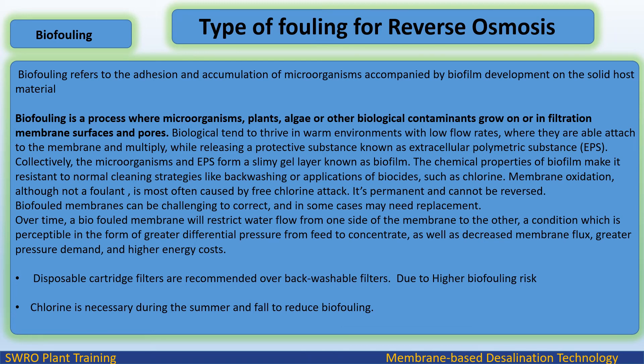Over time, a biofouled membrane will restrict water flow from one side of the membrane to the other, a condition perceptible in the form of greater differential pressure from feed to concentrate, as well as decreased membrane flux, greater pressure demand, and higher energy costs. Disposable cartridge filters are recommended over backwashable filters. Due to higher biofouling risk, chlorine is necessary during the summer and fall to reduce biofouling.